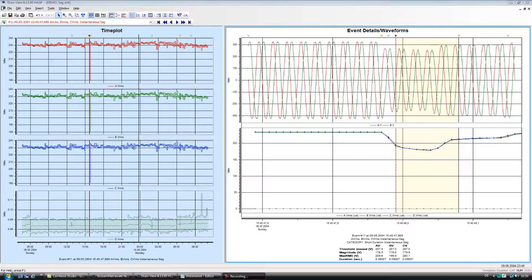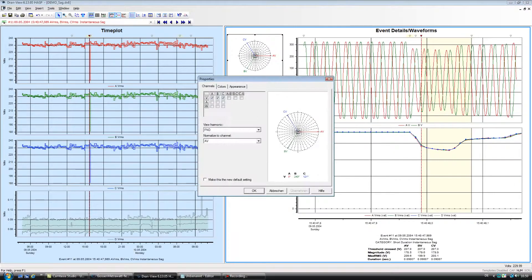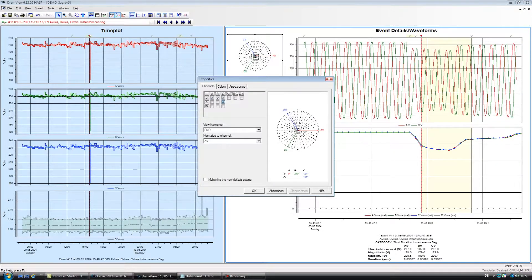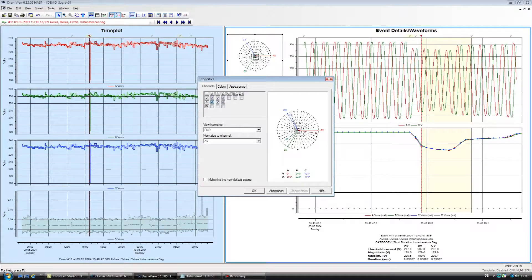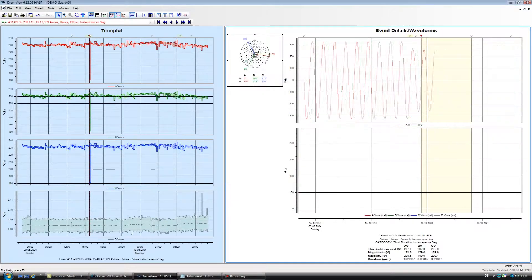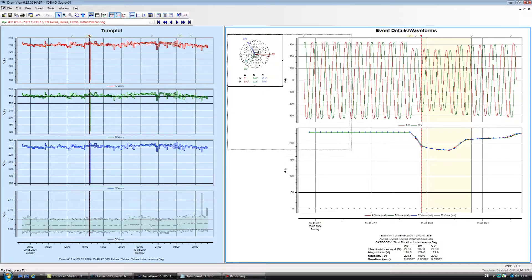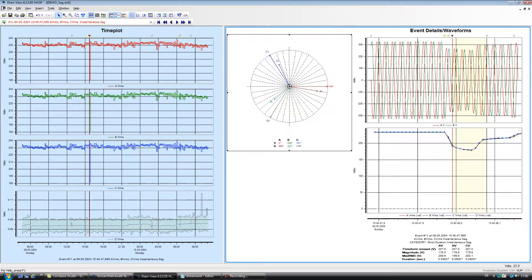Phasor Diagram. With the push of a button, Dran-View generates a phasor vector diagram showing the phase relationship between voltage and current on any channel. This image will help in both making sure the instrument was connected properly and also during your analysis.